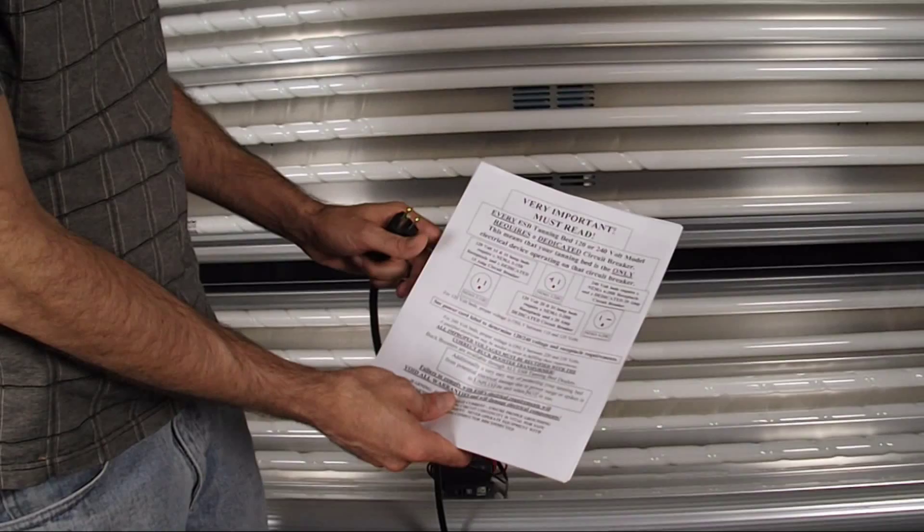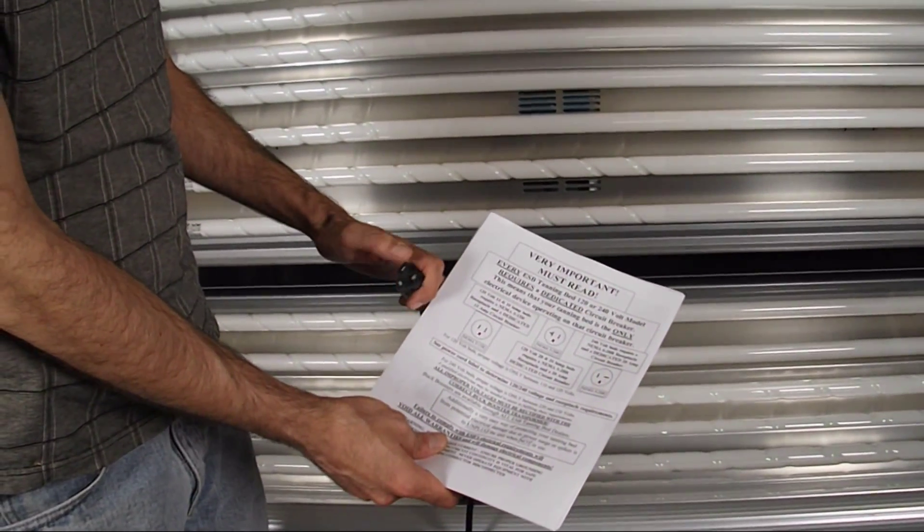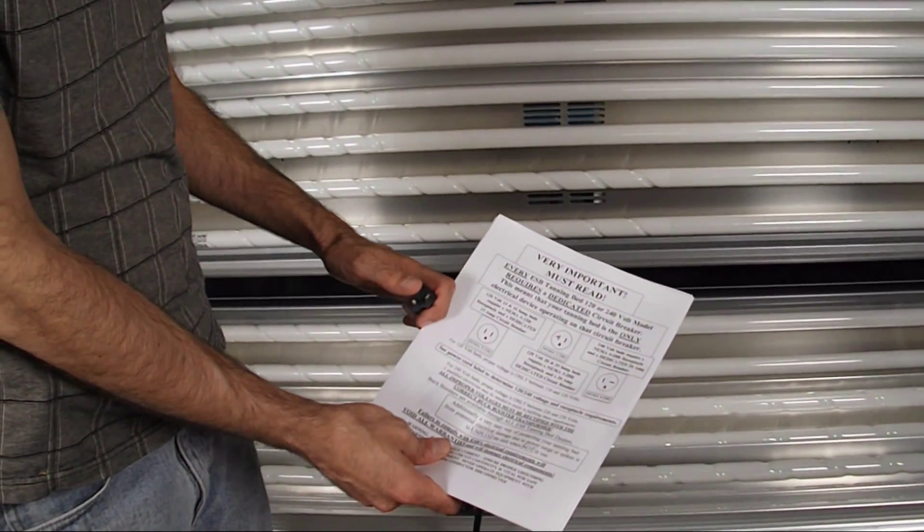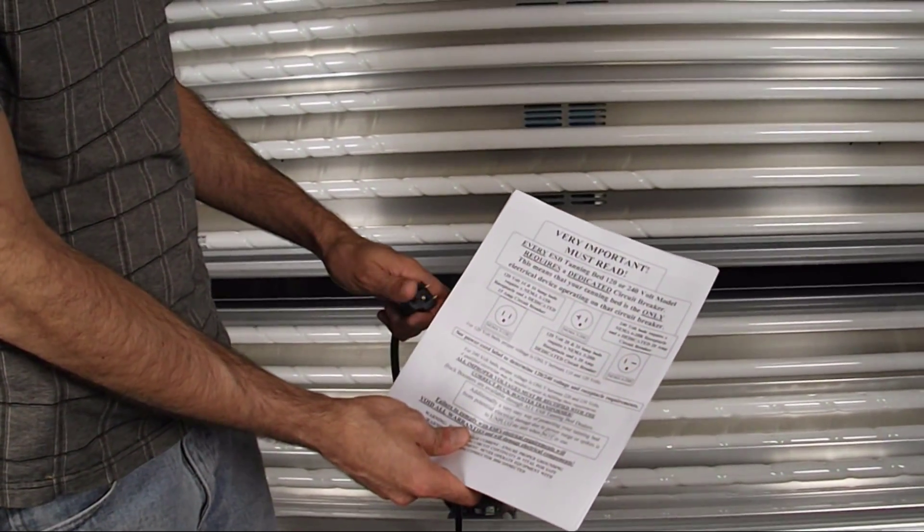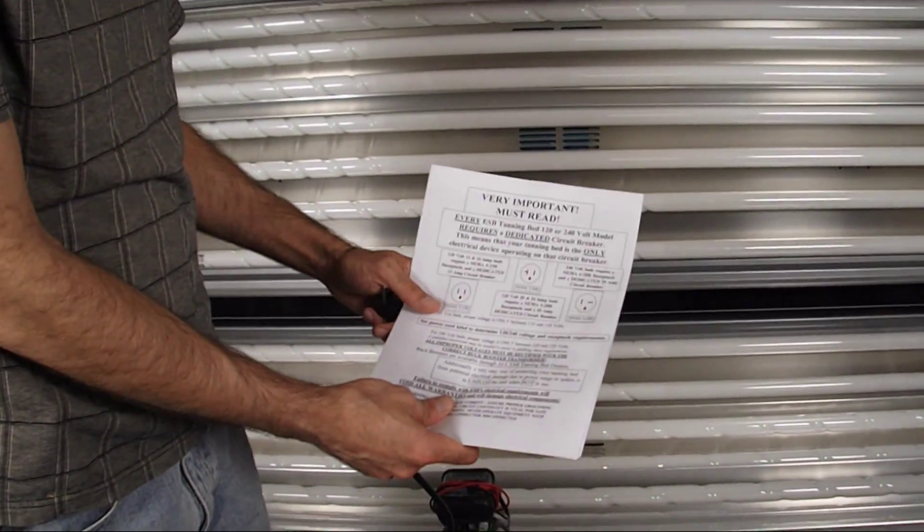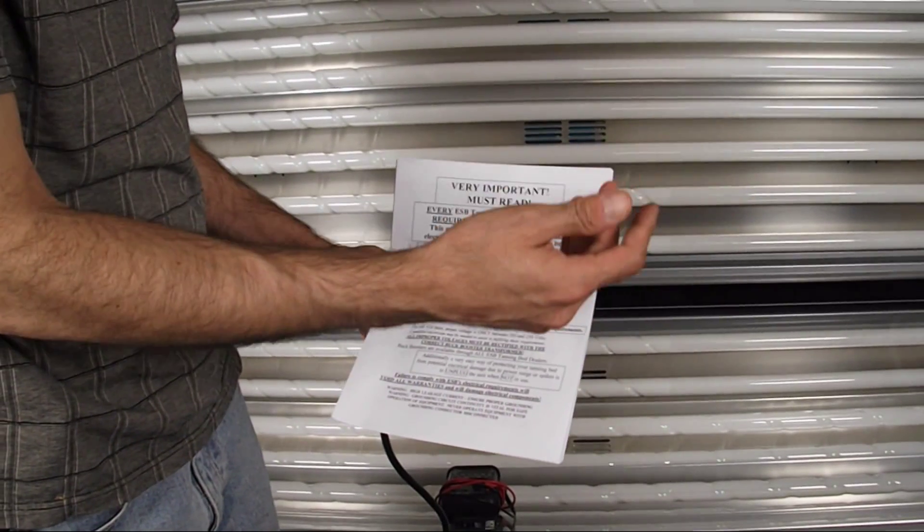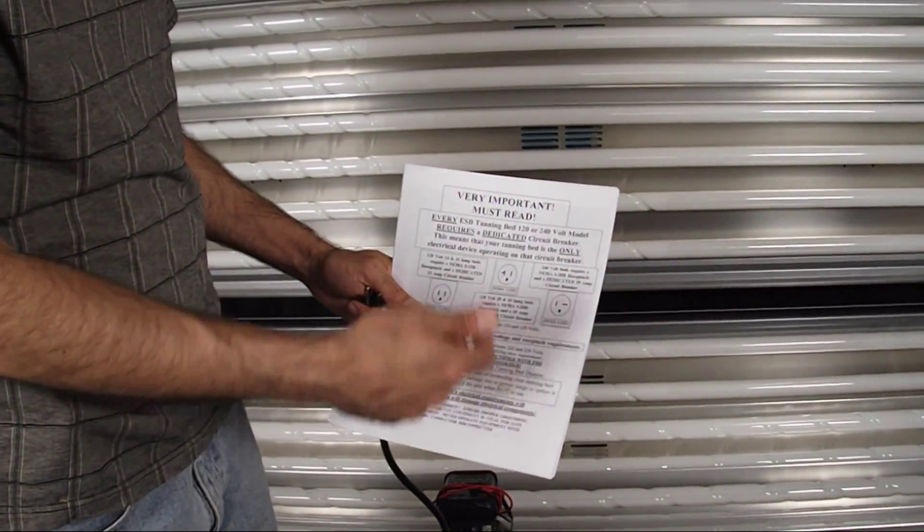There are many older models that might have had a 15 amp plug like this, but they would still require a 20 amp circuit breaker. This is because of the inrush. When you first turn the tanning bed on, you would basically need a little bit more clearance, a little more tolerance in that breaker to prevent it from tripping when you start the bed up.